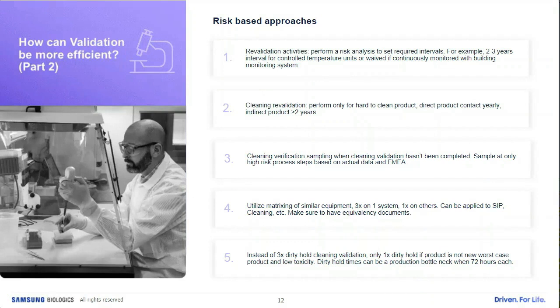If you do a risk assessment and say, okay, my -70 freezer has multiple building management sensors and thermocouples installed that are continuously monitoring it 24 hours a day, 7 days a week, alarmed and monitored, and the system is maintained by calibration and maintenance, do I really need to revalidate that freezer at all when I'm already monitoring these systems?